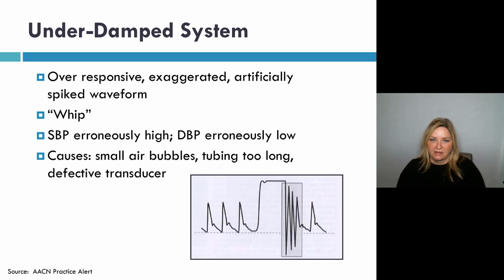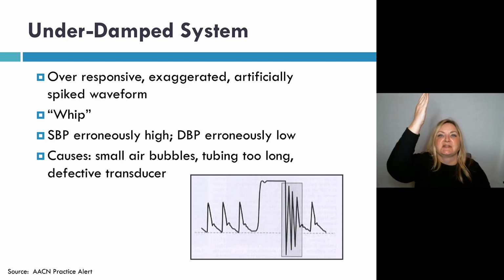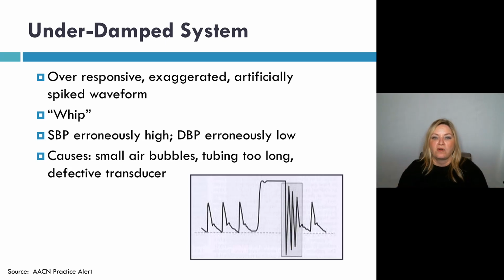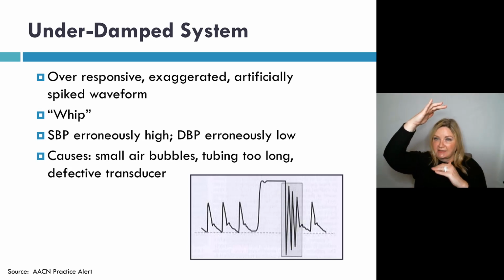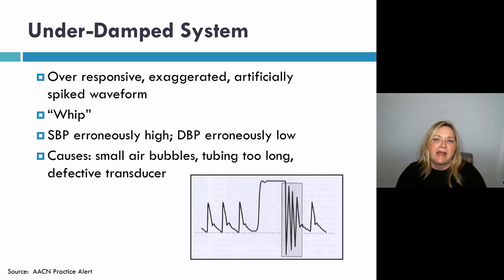With an underdamped line, a lot of times we'll say this catheter has a whip on it, and you'll see an artificial spike in the waveform. In this case, the systolic will be erroneously high and the diastolic will be erroneously low. Microbubbles are the classic cause of this. Also, too much tubing on your line can be the problem, or a defective transducer. So usually it's either bubbles or tubing that are the issue.